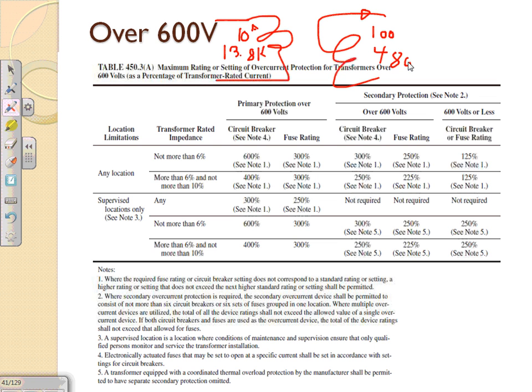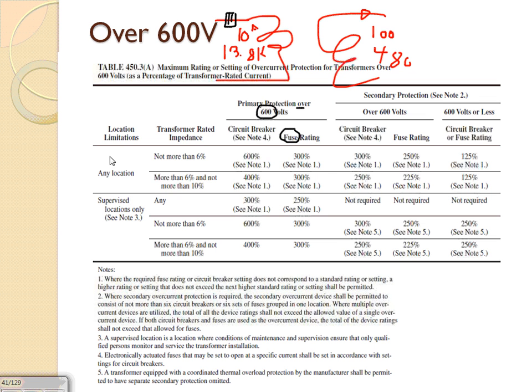Here's my transformer, and I put in the amps just to make the calculation easy. I'm going to size a fuse. That's this table, sizing fuses or circuit breakers. Let's go to the high voltage side. If I go to the high voltage side right in here, I need a fuse right in here. Let's say the primary voltage is over 600 volts. Am I using a fuse? Yes. This is a location exposed to the public, not all other locations, so I can apply it. Your default is right here, and I'm using a fuse.